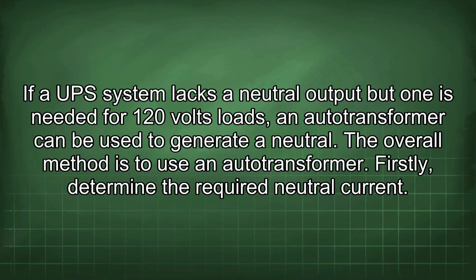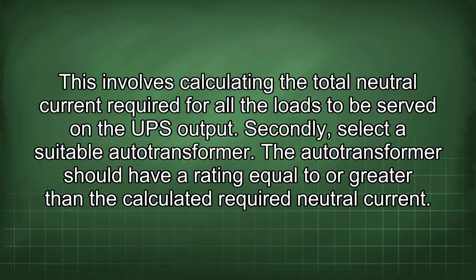If a UPS system lacks a neutral output, but one is needed for 120 volt loads, an autotransformer can be used to generate a neutral. The overall method is to use an autotransformer. Firstly, determine the required neutral current. This involves calculating the total neutral current required for all the loads to be served by the UPS output.